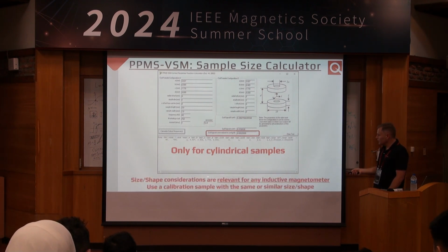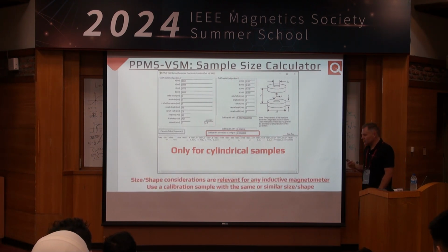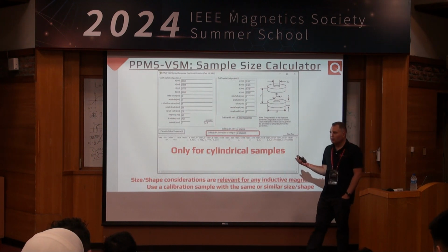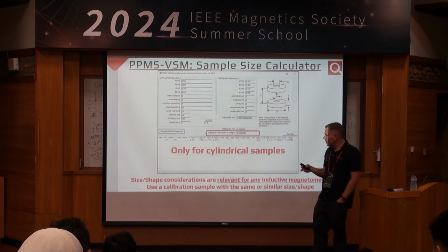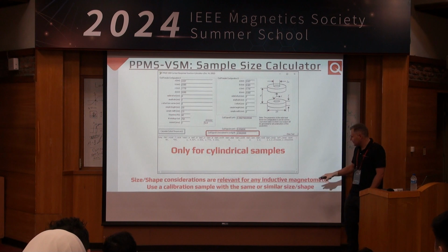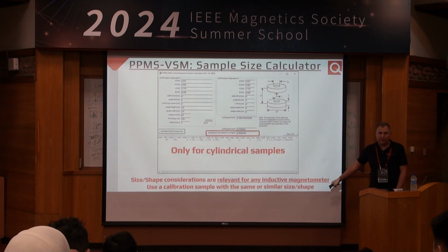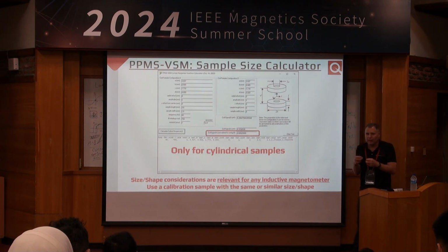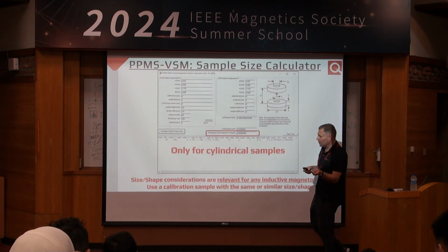Size and shape considerations are relevant for any inductive magnetometer. So those of you using a more traditional VSM, ideally you want to use calibration samples with the same or similar size and shape as your sample. And you can always go through that Gedanken experiment. Imagine you had a sample which is very large and is vibrating. Well, the moment would be very small because you don't have any changing flux in your gradiometer. Same thing goes if you have very small samples.